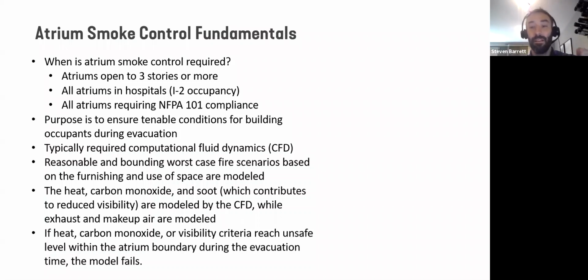And tenability is that last bullet. If the heat, carbon monoxide, or visibility reach a certain level, an unsafe level, within the atrium boundary at any point at 6 feet above the walking surface, then the model has failed. So basically, we have to provide tenable conditions throughout the length of occupant evacuation, including a safety factor.